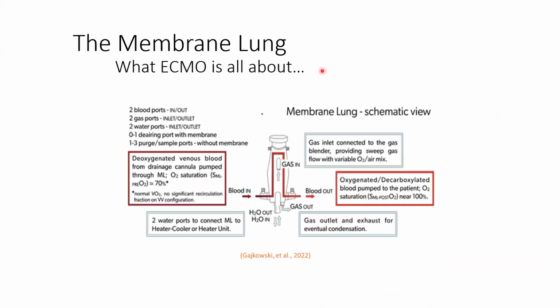The membrane lung, and this is really what ECMO is all about. How does this work? Well, it's very simple physics. You have several inlets on this thing. You have the blood inlet that goes onto the face of the oxygenator. That is venous blood. That blood is going to go around the fibers. You're going to have gas that's connected to a flow meter that you can set from 21 to 100% oxygen. That's sweep gas. That gas is going to go through the fibers.